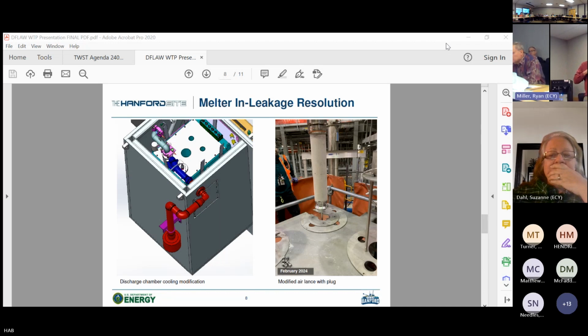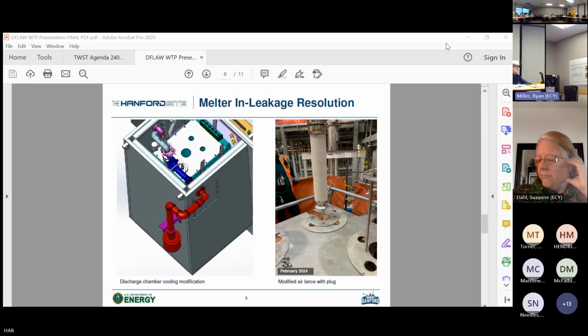So we have those all set when it was cold. But we recognize we're going to have to validate them when it's hot, and there probably will be some adjustments on those interlocks. And all of that testing will have to occur prior to actually introducing the simulant that would create the chemical hazards like NOx. So that's why these are all very critical steps: to make sure that we've got the right flow with the right vacuum, make sure that the system can run in auto, and make sure that we can then validate all of those, they're called safety instrumented systems, the SIS test, the safety instrumented function, so that those all happen in the right timing so that when they occur, first of all, the off-gas system operates properly, and second of all, you burn off the cold cap in a safe way.